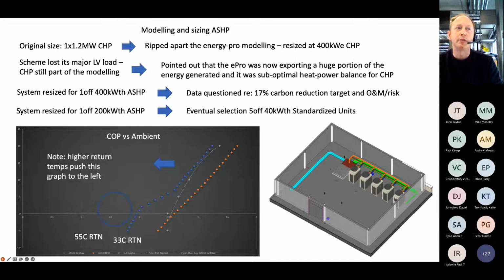So they originally sized at a 1.2 megawatt CHP. We kind of ripped it apart and ended up with something that was a lot more realistic for a 400 kilowatt CHP. The scheme developed and it lost a leisure centre that was a large portion of its low voltage energy load. And again, they were still modelling based on a 400 kilowatt CHP, and we pointed out that the Energy Pro modelling was exporting a huge portion of electrical energy being generated, and it was sort of a not balanced heat power balance that was appropriate for CHP. And it took us to point this out at the 11th hour, the fundamental point that the model didn't account for basic economics.